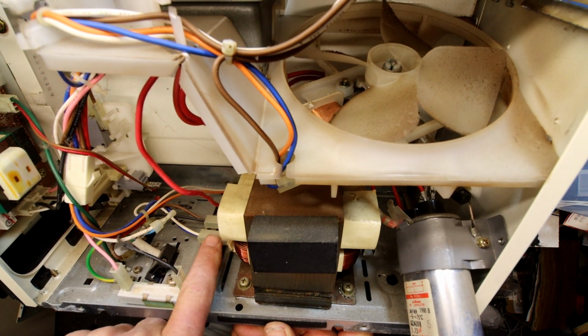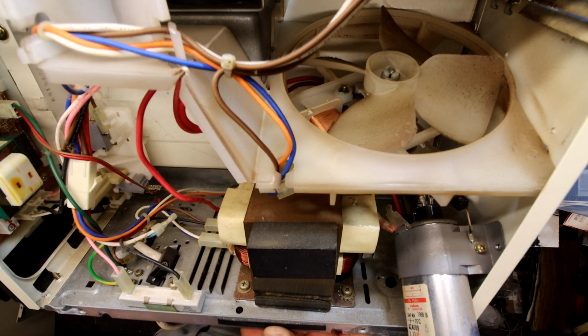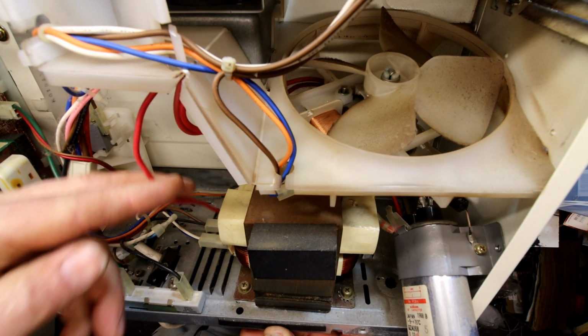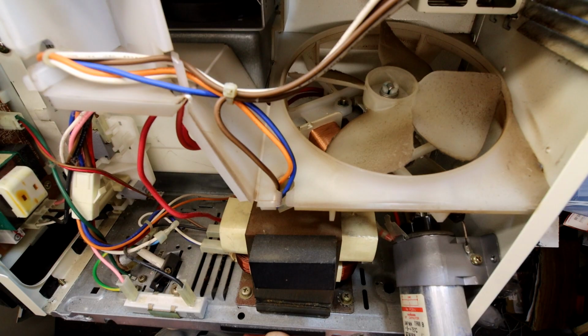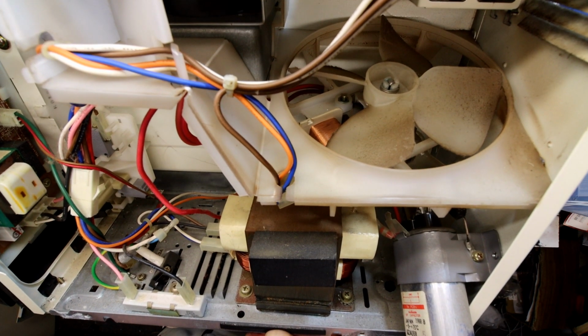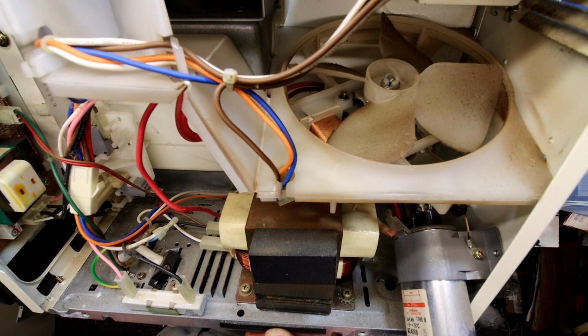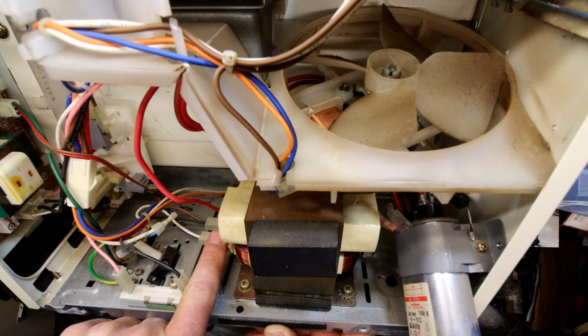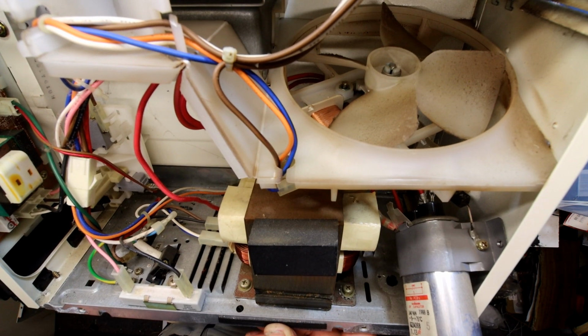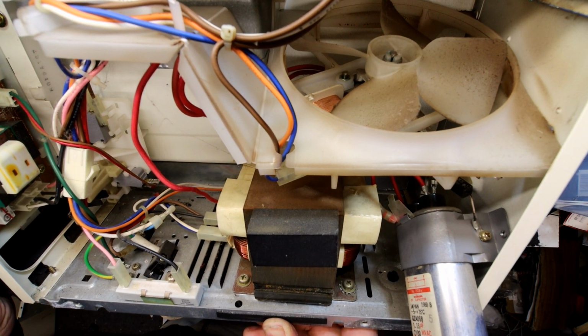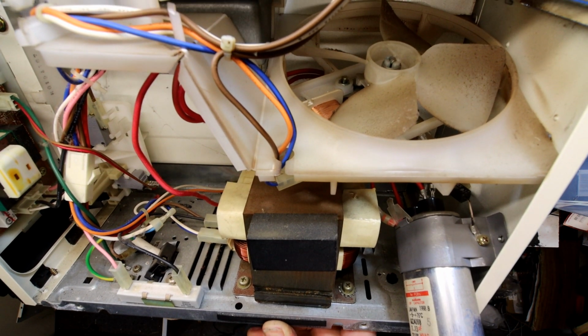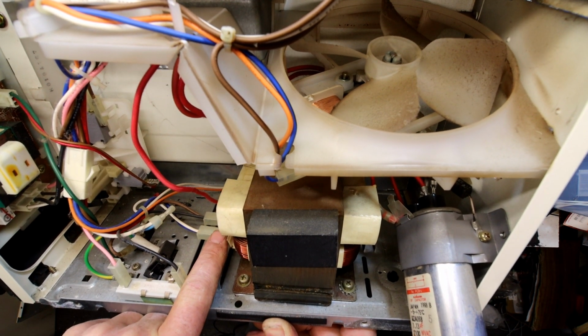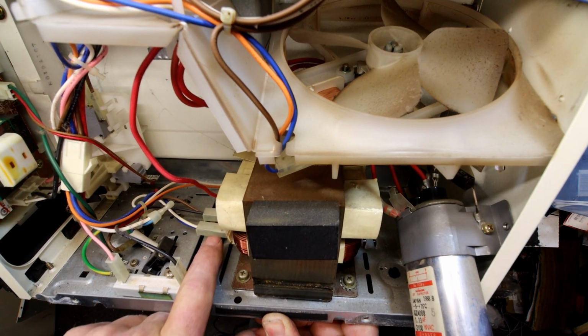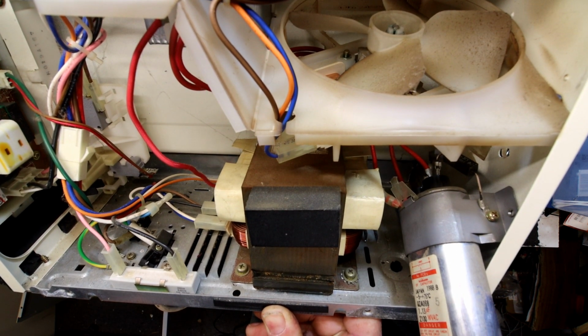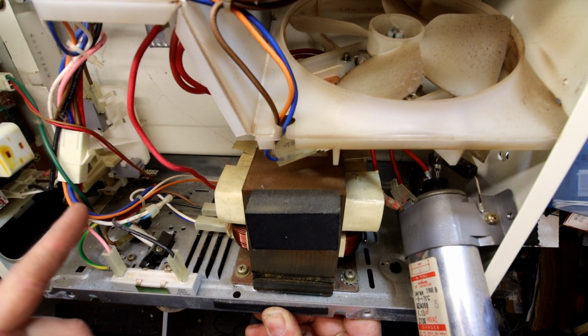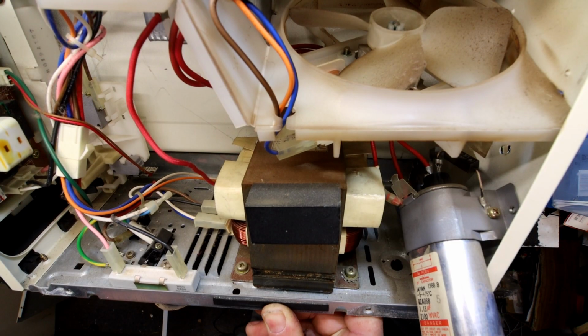Now obviously all these transformers have a primary side, these two terminals here, away from the high voltage, even though this has got a high voltage filament probably going up to the magnetron on the same side. You've usually got this lower winding, doesn't have any connections to the high voltage section, and of course if the oven's going to run you need the controller, whether it's mechanical or electronic, with a control panel to set the time and stuff. That has to put 240 volts into these things, so if the high voltage doesn't fire at all, check you've got 240 volts there. Here's another thing you should really check, so that can be a fault with maybe door switches or the actual controller.